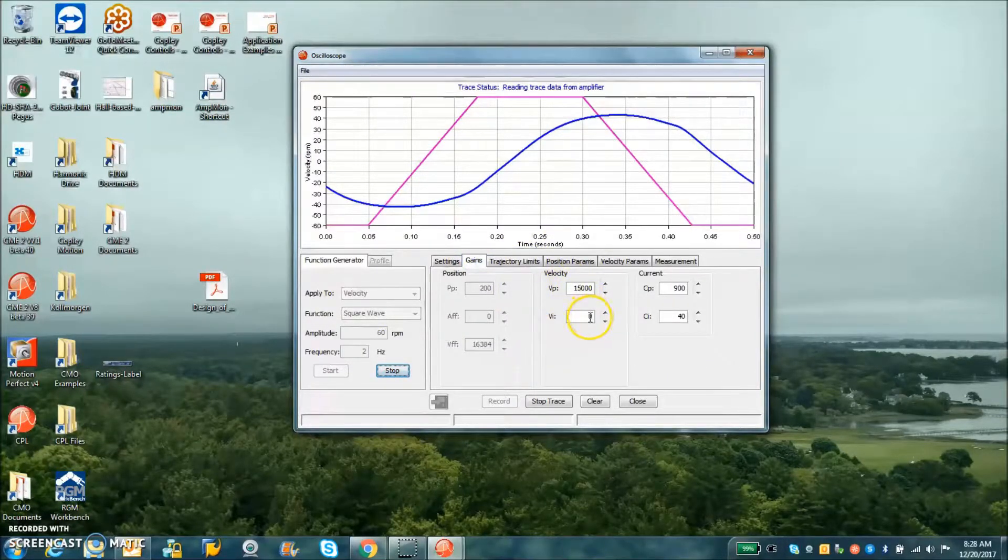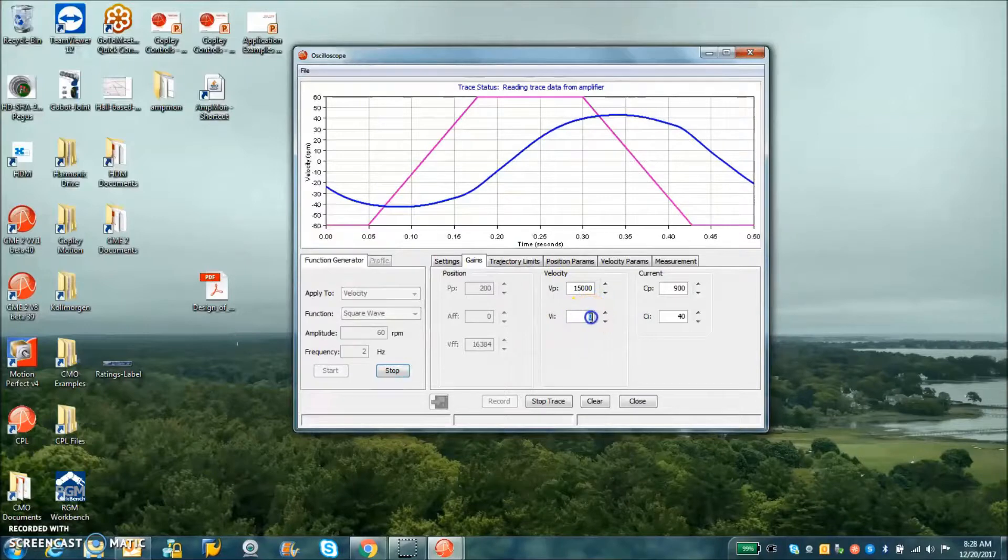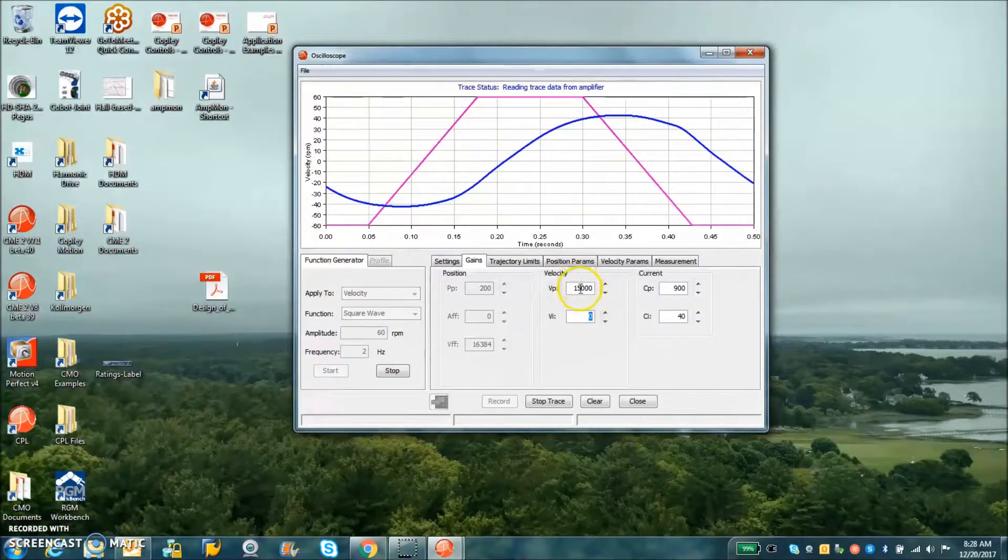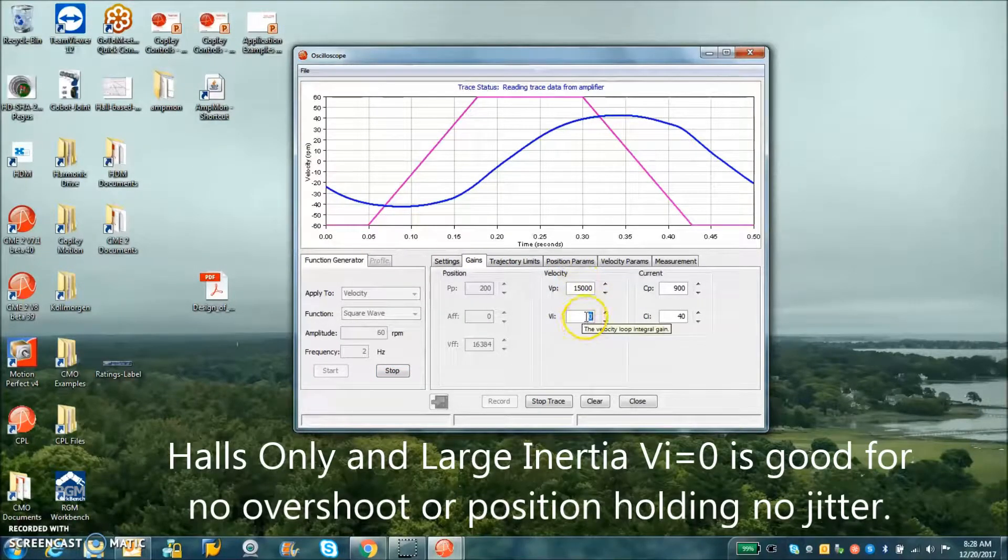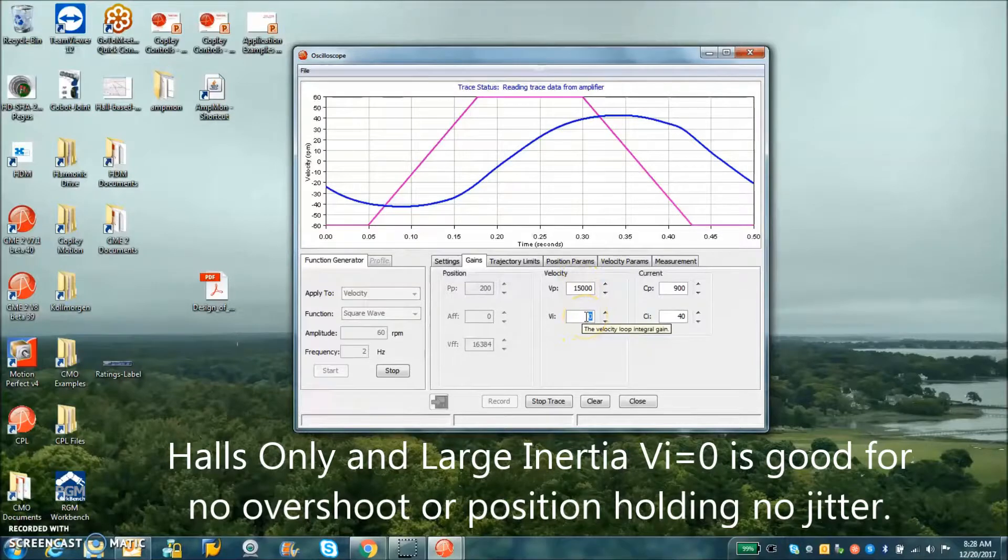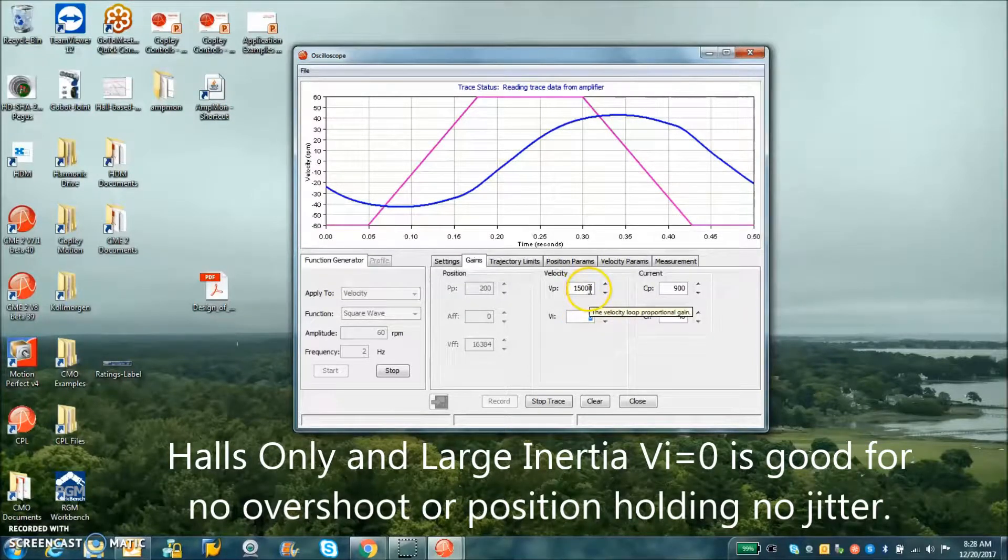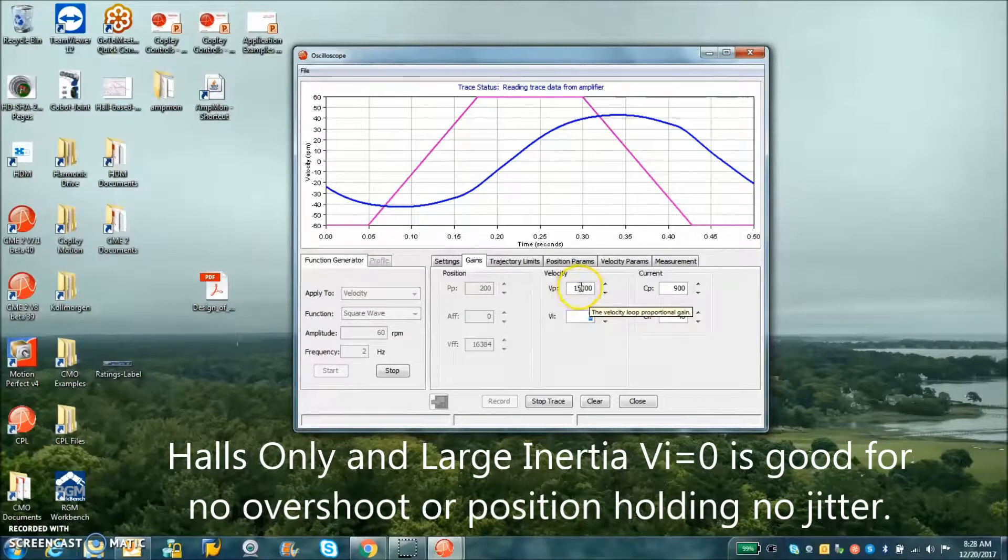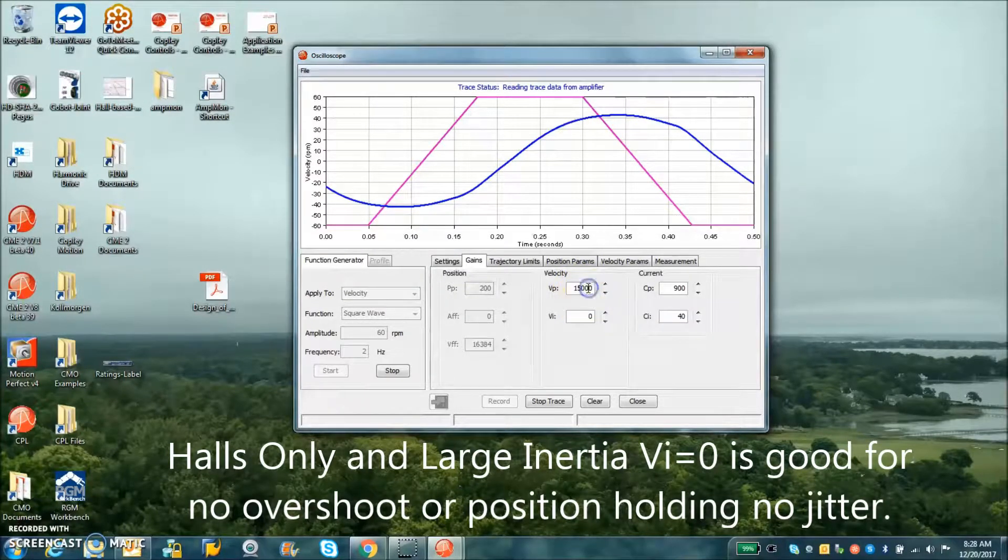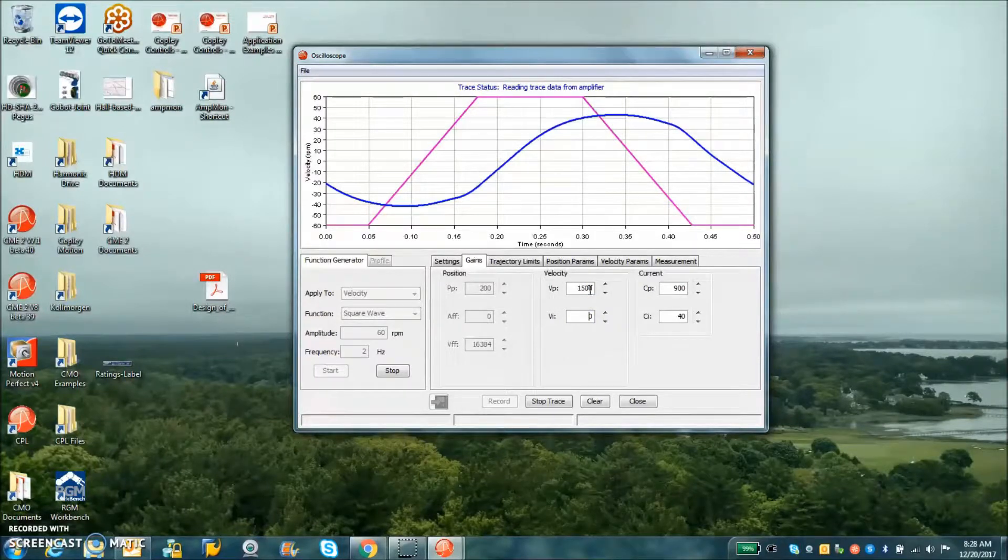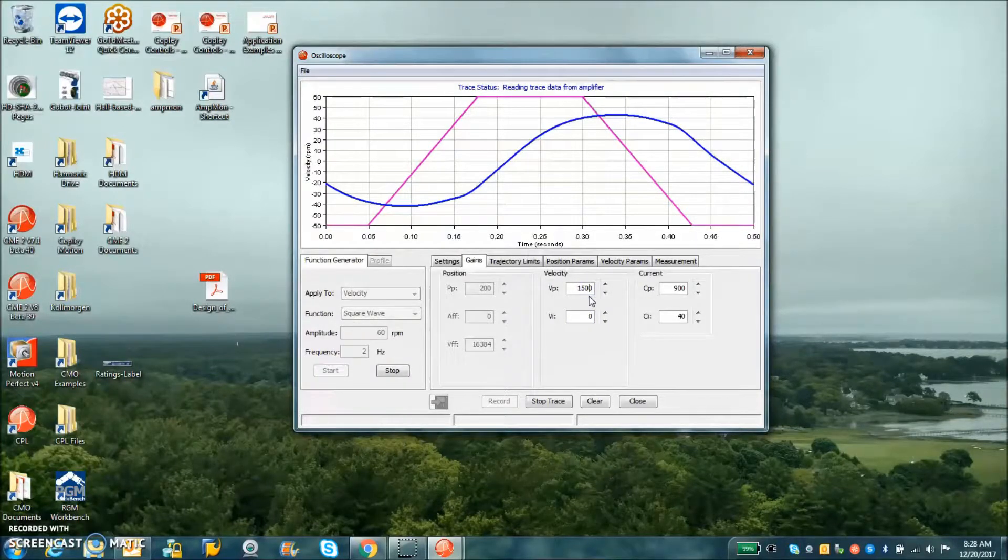Still a little aggressive but the velocity loop tuning, I don't like the overshoot. For halls only, I'm going to set the integral to zero. This is well behaved with no overshooting. If the gains too low of course you don't get any motion out of it.